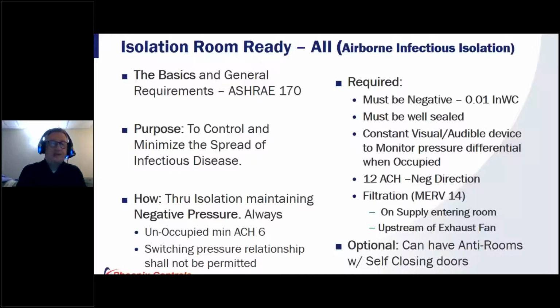In today's world, having an AII, or an airborne infectious isolation room, the basics and the general requirements are pretty specific, and they're pretty clear, right? Per ASHRAE 170, the whole point of an isolation room is to control and minimize the spread of the infectious disease, right? And so when you have a space, in order to, again, protect the staff, protect the patient, and minimize its spread from the public into the corridor, how do you accomplish that? You accomplish that by negative pressure, right? And so the criteria from CDC and ASHRAE 170 is isolation by maintaining a negative pressure, always, right? So unoccupied, you're able to turn those down with 6 air changes per hour, some of them down to 4.